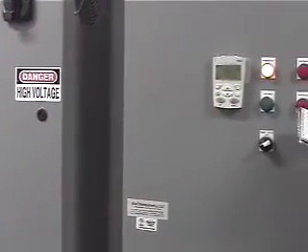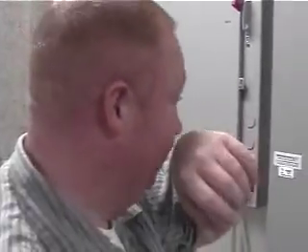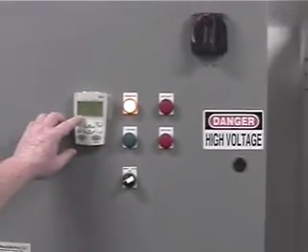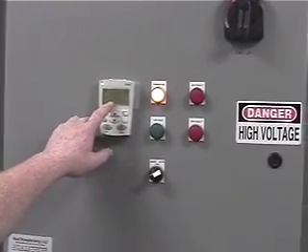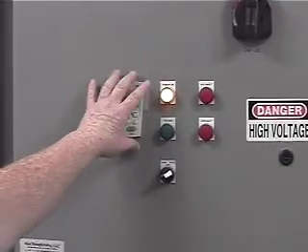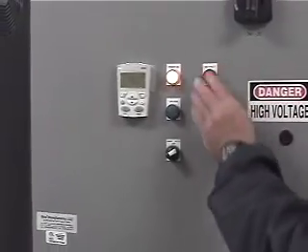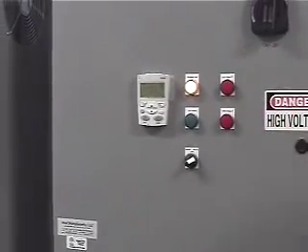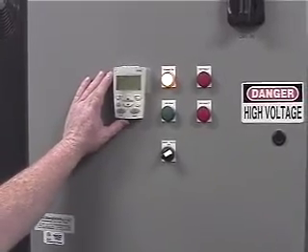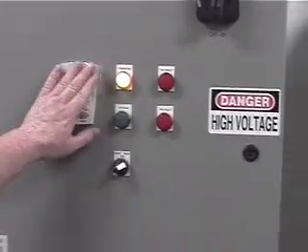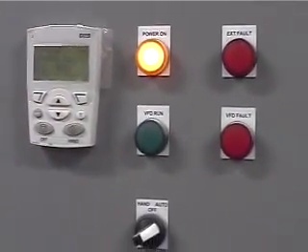But then again, when you're not showing the exterior fault. I'm not an expert with this, so I don't want to explain too much with them. But you're right, now you're in a fault because I'm not giving you a start command. We'll have to talk with them about why it shows a fault. Exactly, because it should show a fault. Why aren't we showing it on a line? It should be an external fault. Well, it's actually not even a fault. We're just not calling for the chill water pump to run. Okay, so why is this light flashing? Yeah, that's something we would want to talk with them about.